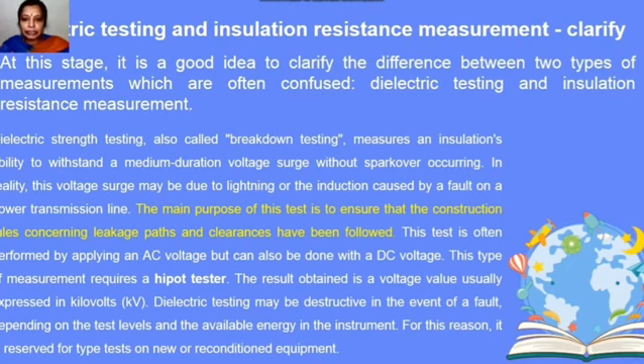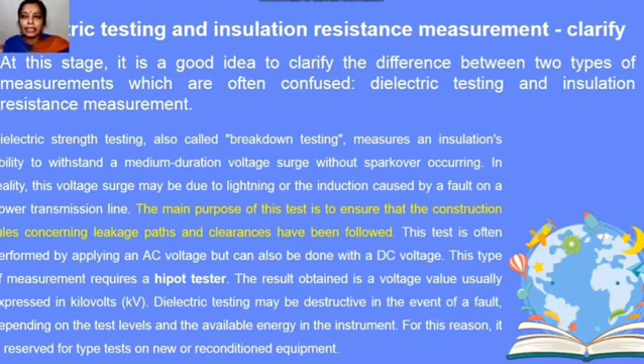This type of measurement requires a high-pot tester. The result is a voltage value usually expressed in kilovolts. Dielectric testing is destructive in nature in the event of a fault. For this reason it is reserved for type tests or on new or reconditioned equipment — type test means a certain sample is taken from a lot and not all samples need to be tested.